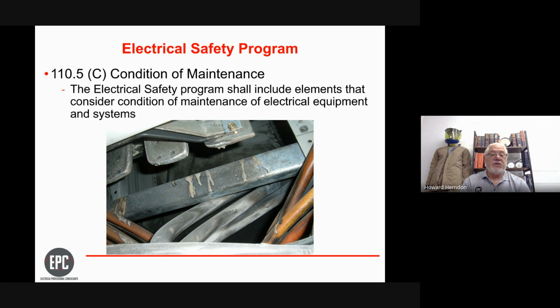And we opened the cover doing an infrared scan and found this inside there. This is one of those hazards that was left for somebody else to find. And after much researching by the facility manager as well as ourselves, we found that an electrical contractor had put a fish tape into this piece of equipment and caused an arc flash event. So can this be a problem? Sure it can. If I was to move those conductors, the insulation on those conductors would probably crack and fall off, thus creating another hazard.